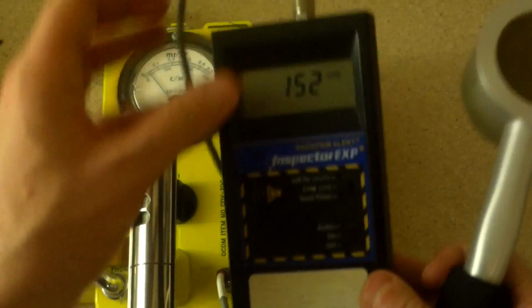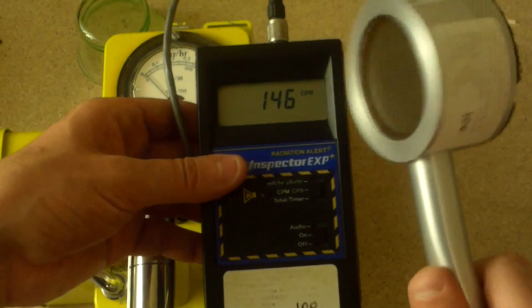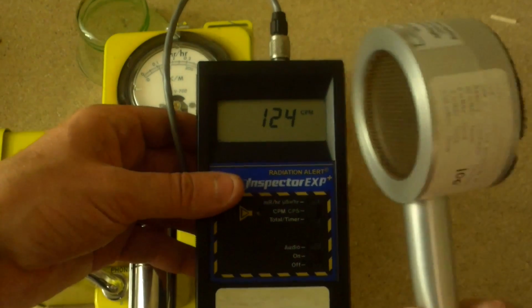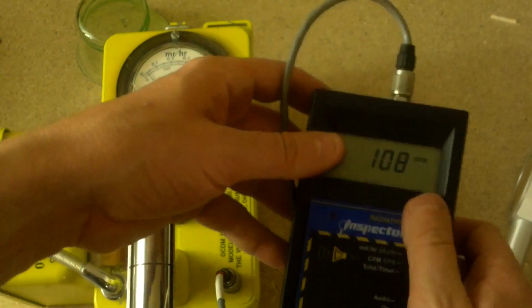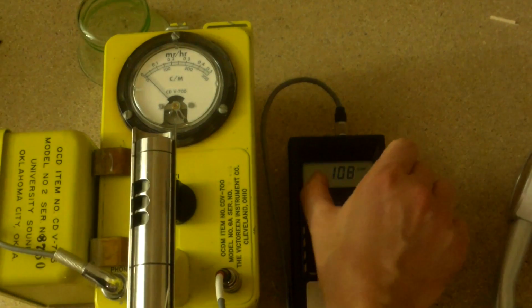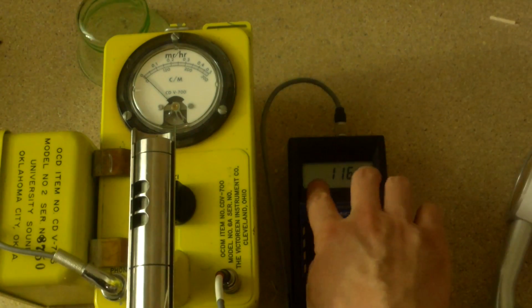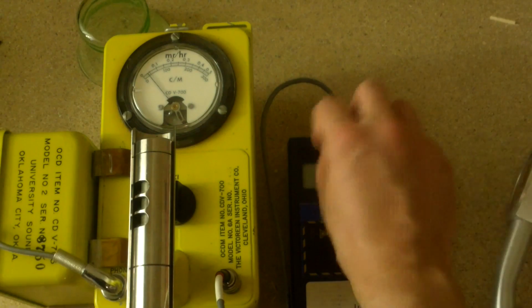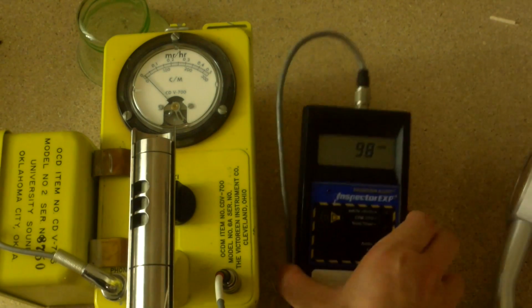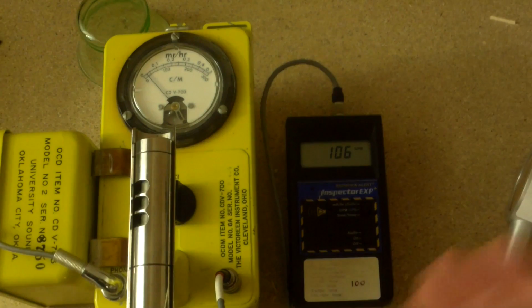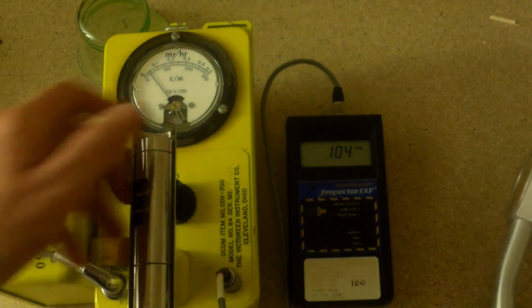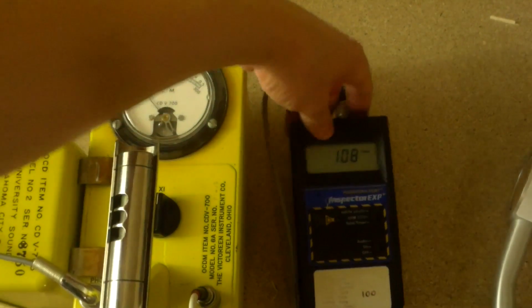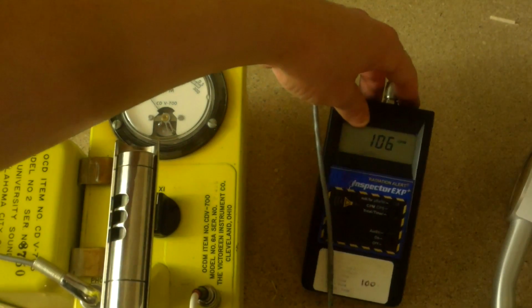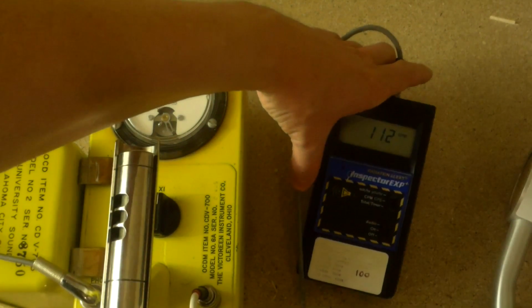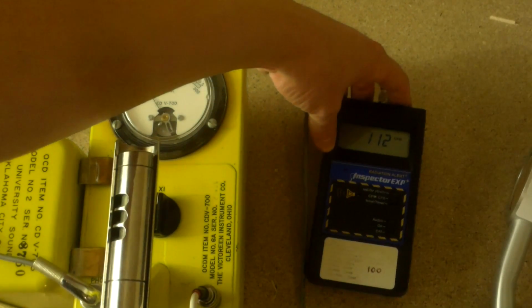Most modern-day units like this one, for example, have anti-jamming. If this gets too high, it cannot read, the same as this one. The difference is this will recognize that it's hit that high level, and it will say something on the screen. They all act differently. Sometimes they say jam, sometimes they say high, sometimes they show the max reading and they beep at you. So they have different ways of showing it, and you should look through your user manual to see what the unit's supposed to do. But my point is this one will say, look, boss, I can't read this anymore. This is a psychotic amount of radiation, but I'm at least going to tell you that that's the reason I'm not able to read anything. It's not because it's not there, it's because I am completely saturated.